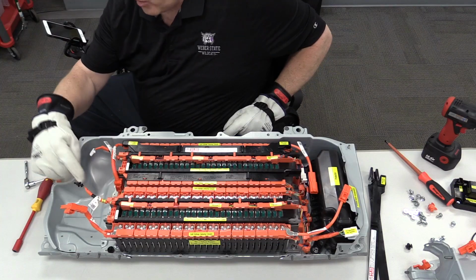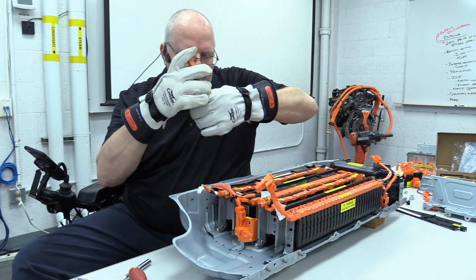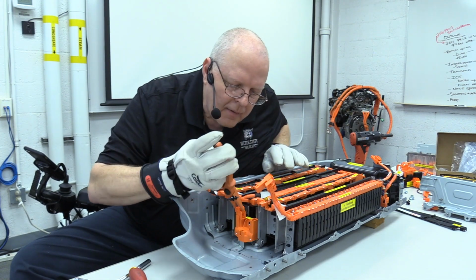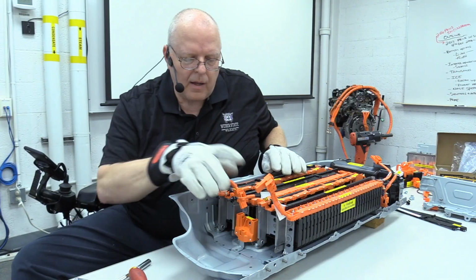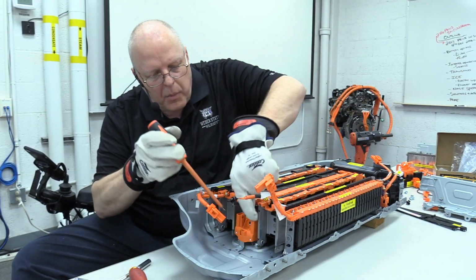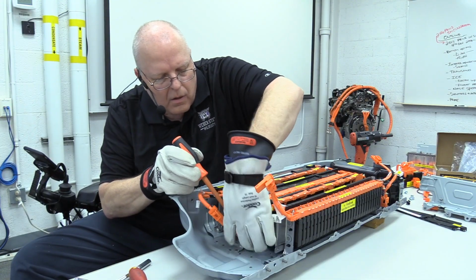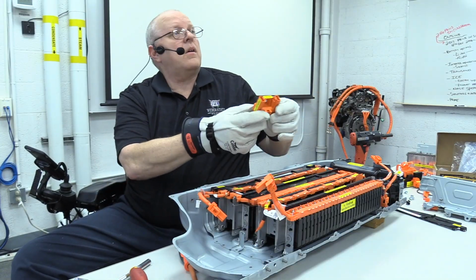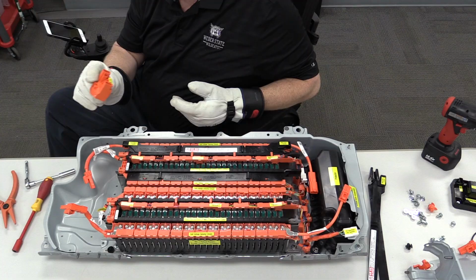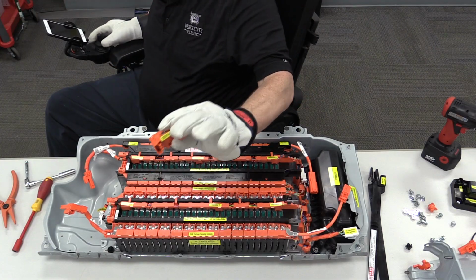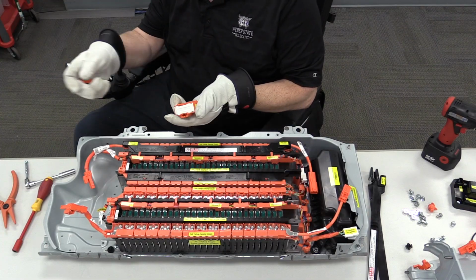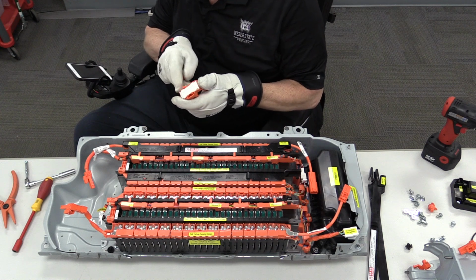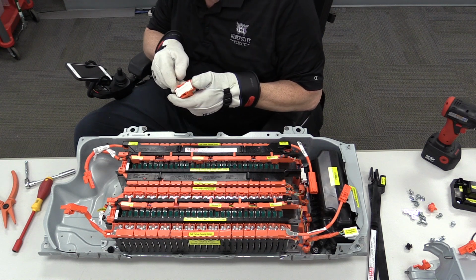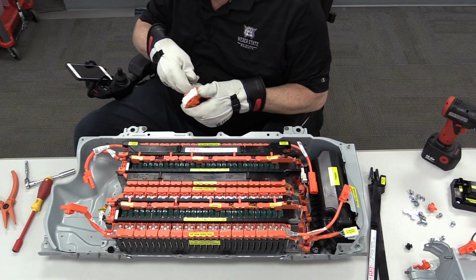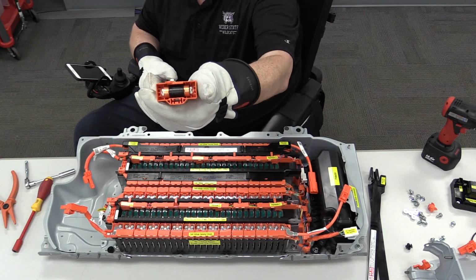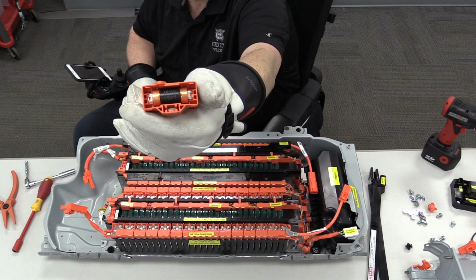And then right here we have our fuse, our high voltage fuse. So we've got one more wire, the positive terminal from the battery stack number 2, that's connected to it. So I can unplug it, get it out of the way. And then there's just a little tiny clip that holds that fuse in place. And up it pulls. So our 125 amp fuse is inside of this connection here. If I grab just a little screwdriver and push up on the white tabs on each side, out it comes. And you can see right in there a 125 amp fuse.